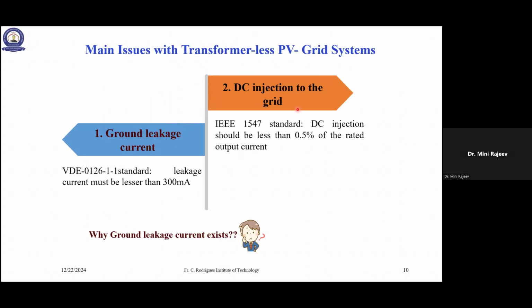Now, DC injection comes if the inverter output is not symmetrical. DC injection means, if the average value of the output voltage or output current is 0, then there is no DC injection. If the output of the inverter has a DC value, then the DC will be injected into the grid. That means the average value is finite. Then DC will be injected into the grid.